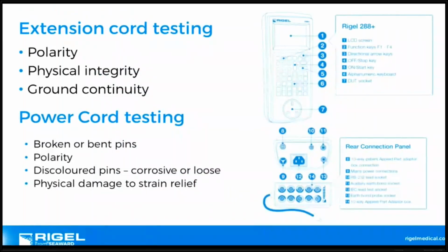One thing which is different from 62353 and 60601 is extension lead testing and power cord lead testing, looking for some typical broken pins, the polarity of the actual cord to make sure that the hot and the neutral are not reversed. Well, the 288 actually has a designated power cord test. This is the mains in here, so your mains plug goes to your main socket. But what this here is for is IEC lead testing. So we plug an IEC lead test into the equipment test socket on the 288, and that's how we test extension leads, and that's how we test power cords.